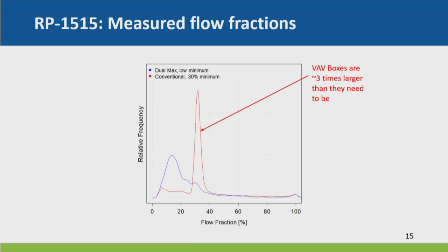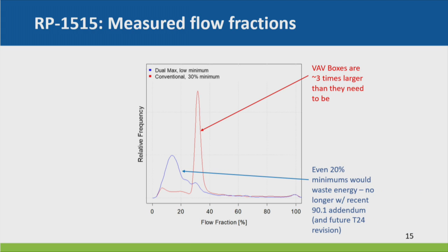And so all the airflows went down, and you can see that from 5 to 10, what is it, roughly 12% maybe average for the building in terms of the airflow. So they all went way, way, way down because the loads are way, way down.